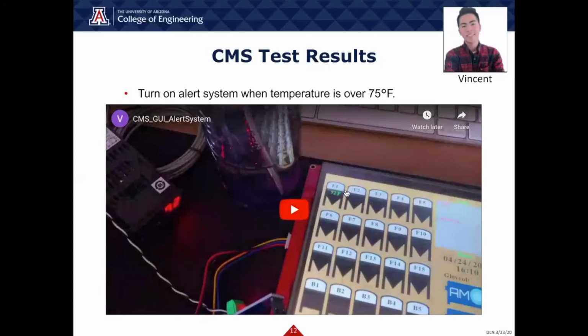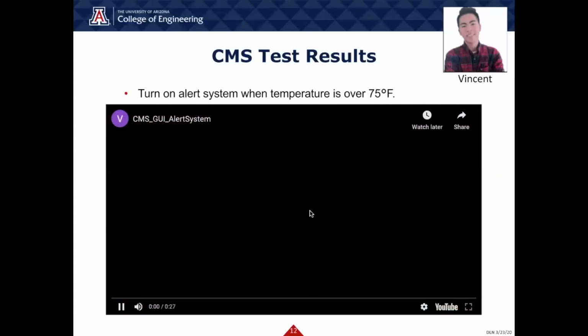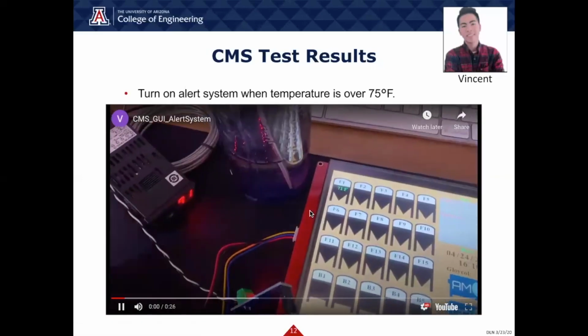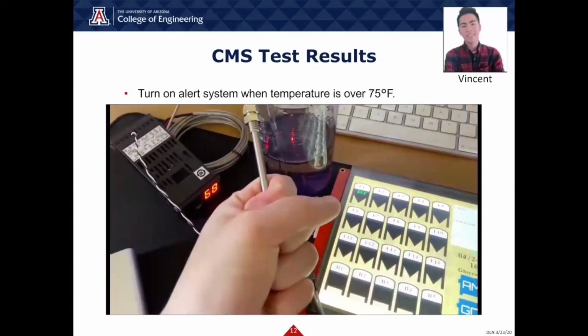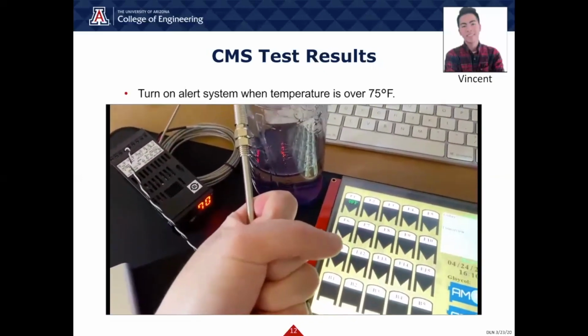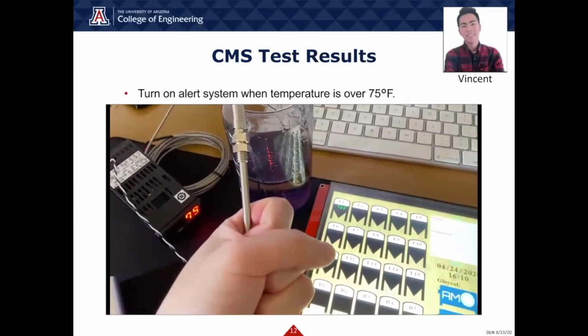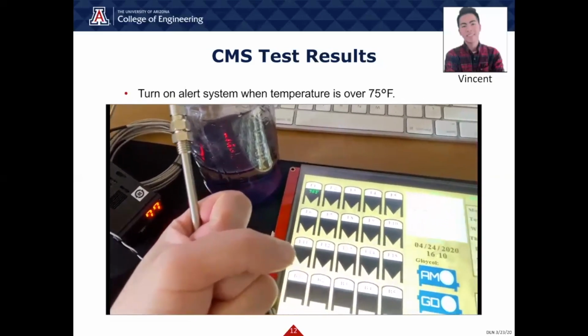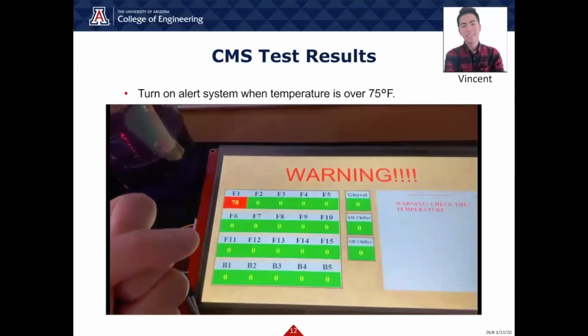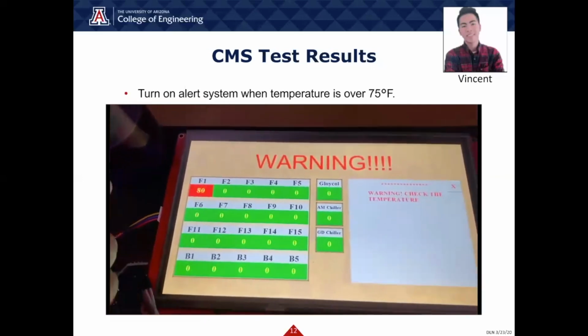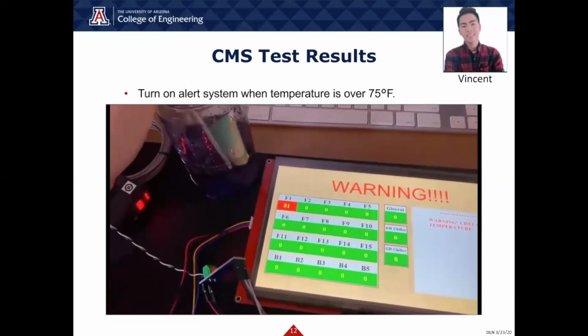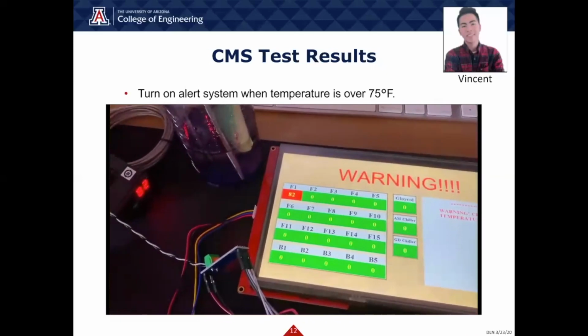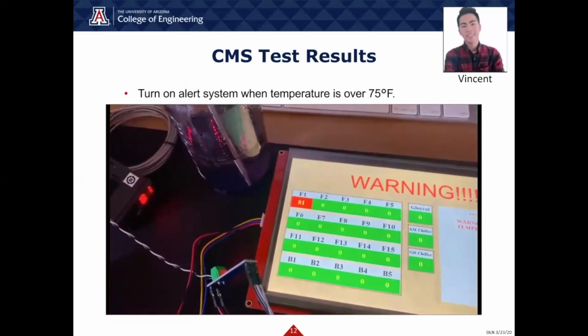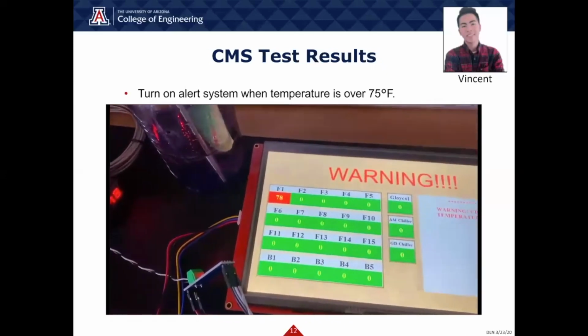We also conducted 2 tests for the CMS. The GUI should turn on the alert system when the temperature is over 75 degrees Fahrenheit. During the test, I held the thermocouple in my hand to raise the temperature. If it's over 75 degrees Fahrenheit, then the alert system is activated. And if I put the thermocouple back in the water, the temperature drops, and if it's less than 75 degrees, then the GUI will go back to the home screen automatically.